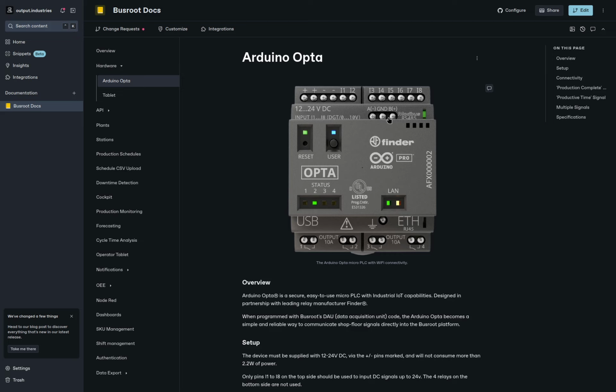We also have connected into things like packaging machines, which go through a cycle for each packaging that they do. For example, inside that machine there might be something that cuts the packaging or finalizes that, and we can tap into that signal and count that. So there's a lot of different options we can use to pull some of the information that we need into this box. It's really a universal box for us. We don't program this box specifically for any customer.